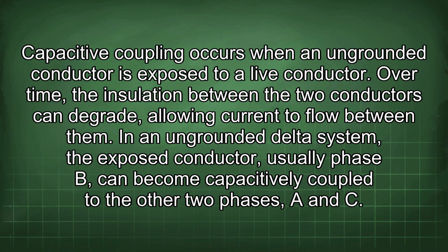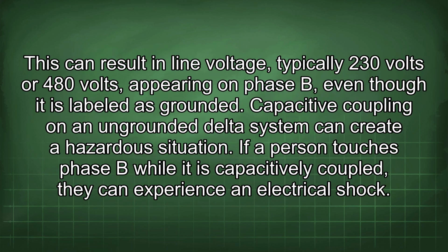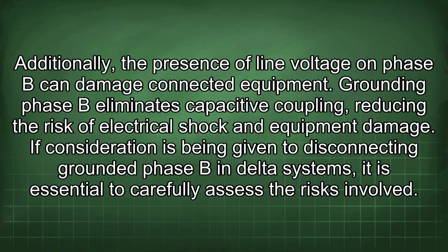In an ungrounded delta system, the exposed conductor, usually phase B, can become capacitively coupled to the other two phases, A and C. This can result in line voltage, typically 230 volts or 480 volts, appearing on phase B, even though it is labeled as grounded. Capacitive coupling on an ungrounded delta system can create a hazardous situation. If a person touches phase B while it is capacitively coupled, they can experience an electrical shock. Additionally, the presence of line voltage on phase B can damage connected equipment. Grounding phase B eliminates capacitive coupling, reducing the risk of electrical shock and equipment damage.